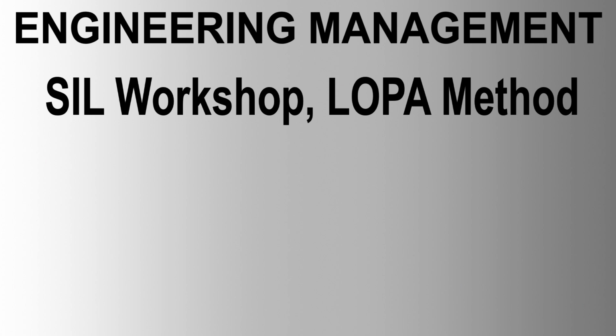Determine required SIL of the SIF. The required SIL rating of the identified SIF is determined in this step. Steps include: select the first SIF, hazardous scenario, to be examined. The facilitator explains the explicit purpose and intent of the SIF, including any safeguards available. The facilitator assesses the first SIF. The SIL rating of each SIF will be identified.